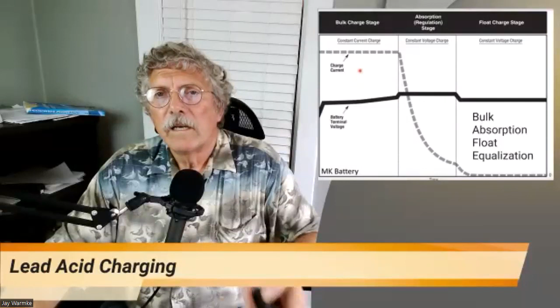So if I've got a 50 amp charger, I'm going to dump 50 amps into it until it reaches a certain set point, typically the set point voltage of the system. The battery's not full, but it's reached its voltage. Now we go into what's called a constant voltage charging process, where it maintains that voltage at a constant level as it eases off on the amperage coming in.